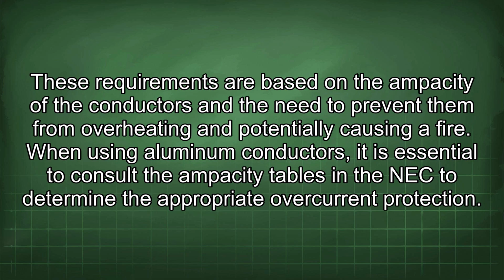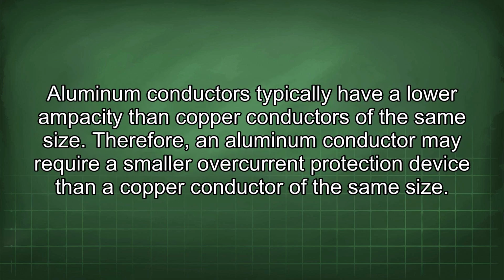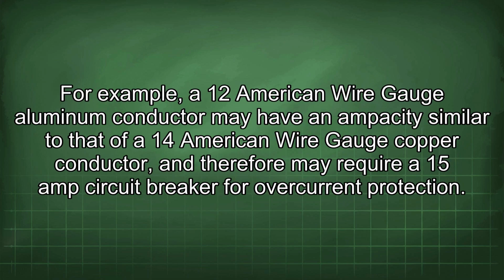When using aluminum conductors, it is essential to consult the ampacity tables in the NEC to determine the appropriate overcurrent protection. Aluminum conductors typically have a lower ampacity than copper conductors of the same size. Therefore, an aluminum conductor may require a smaller overcurrent protection device than a copper conductor of the same size. For example, a 12 American wire gauge aluminum conductor may have an ampacity similar to that of a 14 American wire gauge copper conductor, and therefore may require a 15 amp circuit breaker for overcurrent protection.